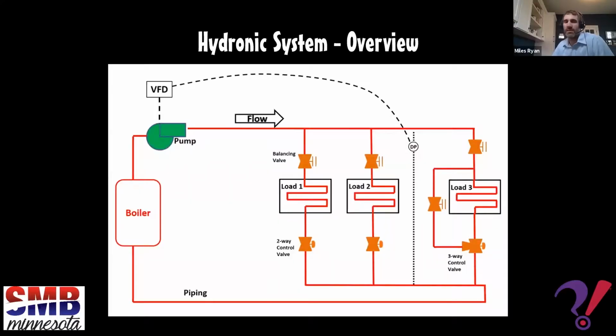All right. Yeah, thanks. So let's kind of transition a little bit into some common hydronic systems. We'll do a quick overview of how these systems are arranged and typically operate. And then I'm going to turn it back over to Mark to talk about some of the common TAB procedures seen on those systems. So here you have a primary only variable speed hydronic system. So it's a hot water system. And when we say primary only, we mean all of the water that's flowing through the primary piece of equipment, the boiler in this case, all that water is also being sent out to the spaces, to the loads in the building, right? It's all one big path there.